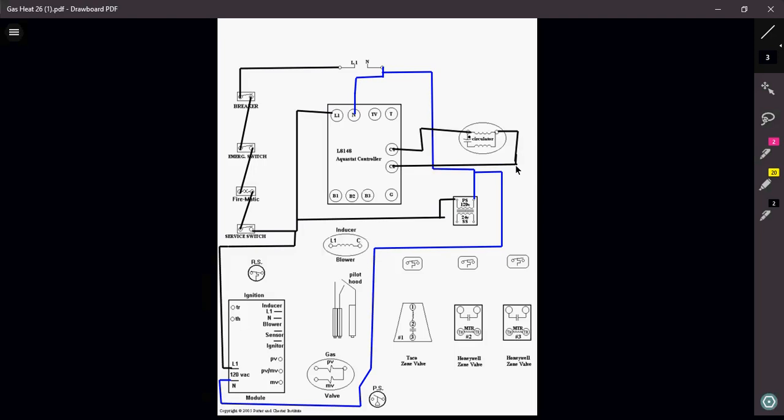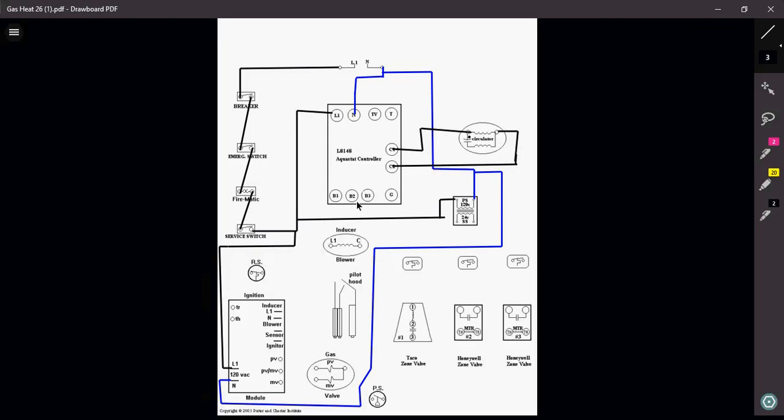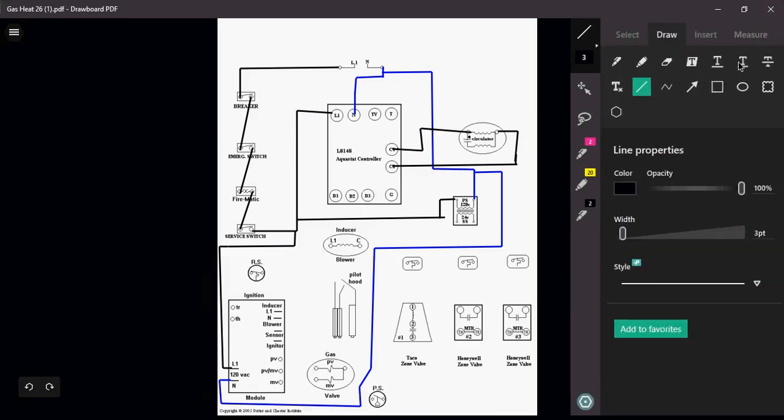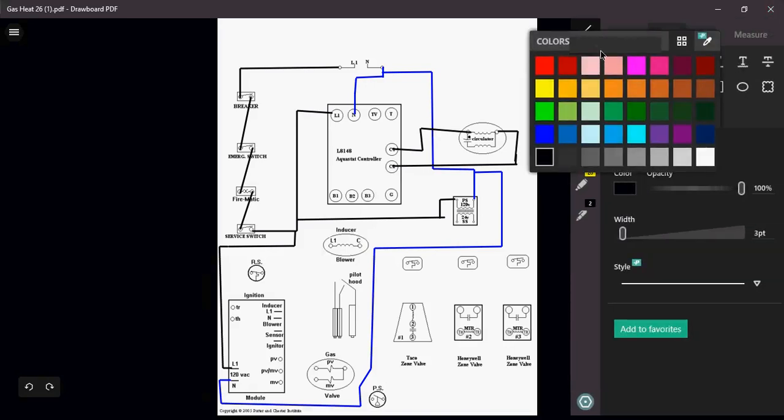Now we're going to take care of our burner circuit. Remember we are now dealing with a triple Aquastat here, B1, B2, and B3. If I was to wire between B1 and B2, I would be wiring it for millivolts. I am not dealing with a millivolt circuit here. I'm dealing with a 24-volt circuit. So between B1 and B3 is my 24-volt circuit.